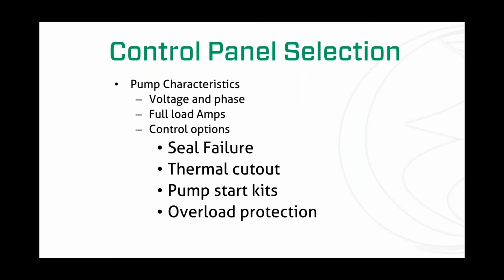By selecting the pumps first, this will help us determine things like voltage and phase. Sometimes the pump you need isn't available in 115 volts. Sometimes the pump you need will be a big three-phase pump capable of moving hundreds, if not thousands, of gallons a minute. Each and every pump is going to have its own set of electrical requirements, and we need to know what those requirements are before we can pick out the right panel.